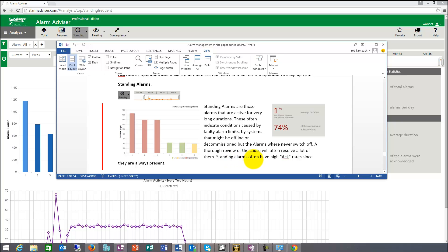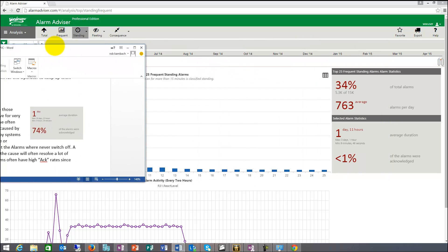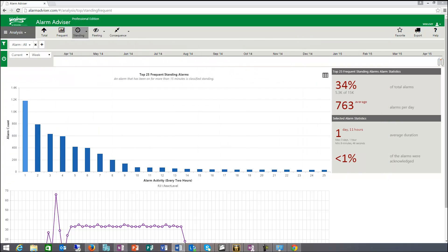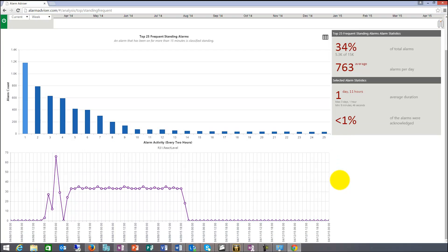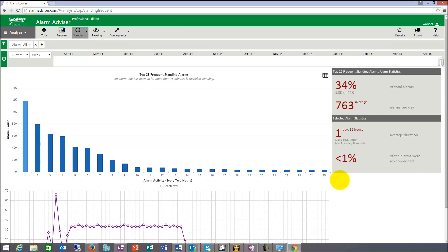Standing alarms often have a high Ack rate since they are always present. So with frequent, they come very often, but standing, they don't come often, they're just always there. These are, whatever control room you go, you always see this long list of acknowledged alarms. And typically those are the standing alarms that basically are always on no matter what the condition of the plant is at that point.